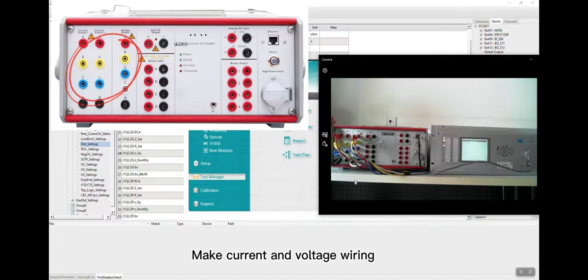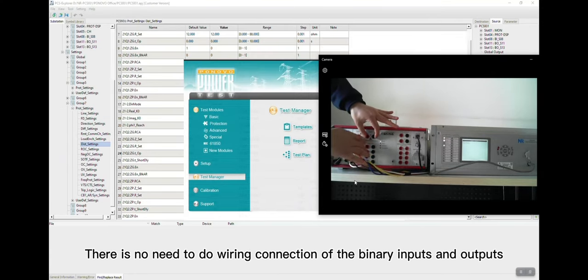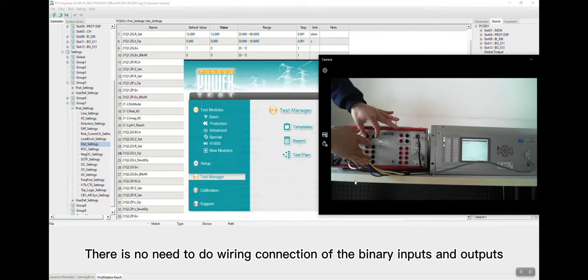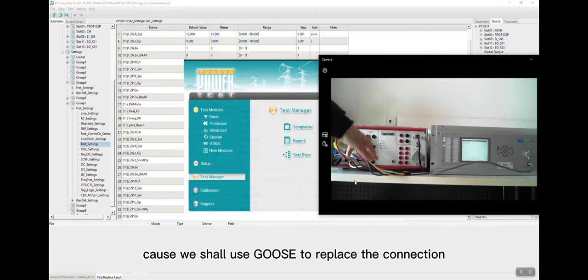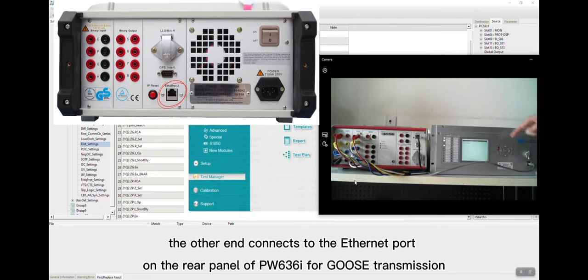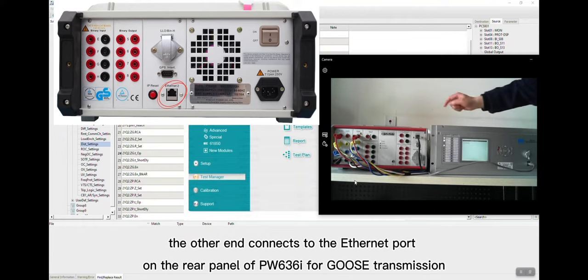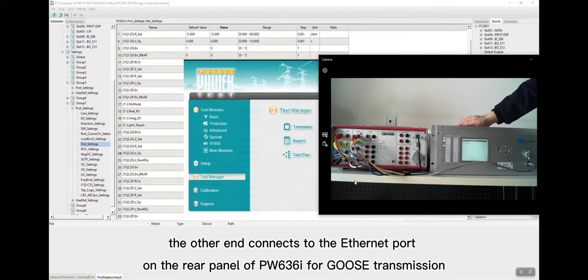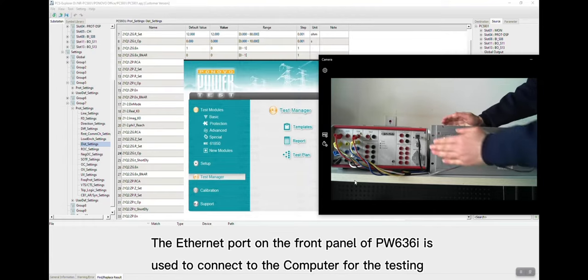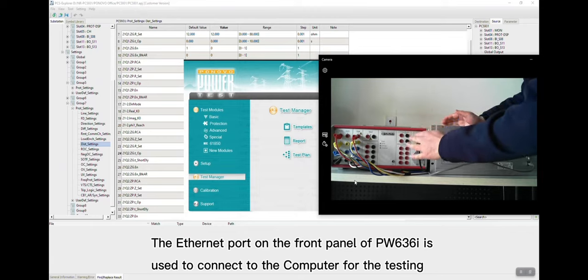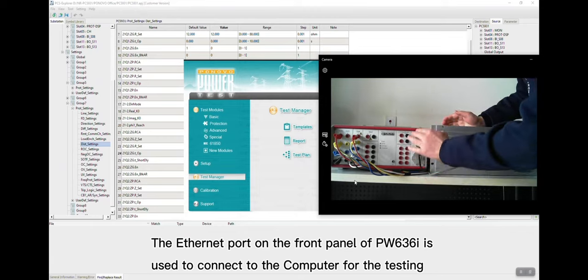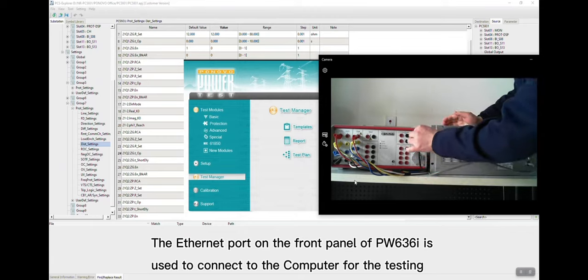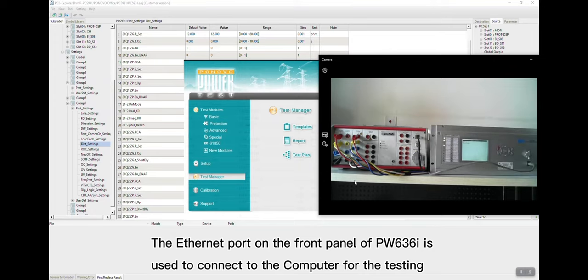Make current and voltage wiring. There's no need to do wiring connection of binary inputs and outputs because we shall use Goose transmission to replace the connection. Use Ethernet cable to connect one end to the relay, the other end connects to the Ethernet port on the rear panel of PW636I for Goose transmission. The Ethernet port on the front panel of PW636I is used to connect to the computer for the testing.